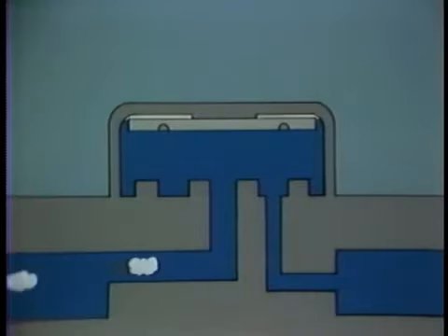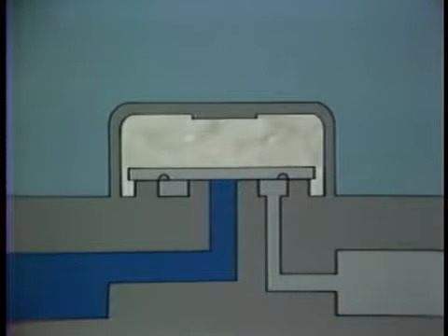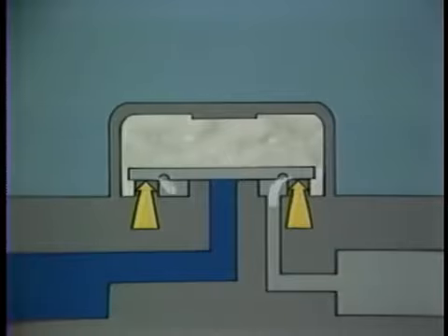Since any gas, including air, causes the trap to close, some provision must be made to remove non-condensables from the control chamber. This is usually accomplished with a rough grind applied to the seating side of the disk, or a bleed passage machined between the control chamber and the outlet.